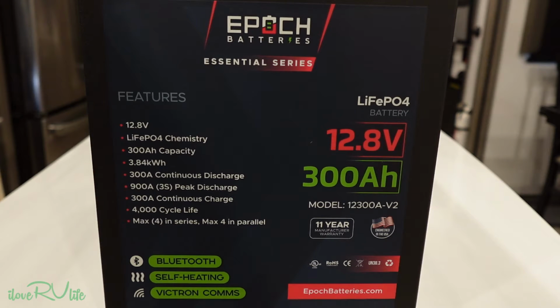As for electrical characteristics, it's a 300 amp hour battery with a maximum continuous discharge of 300 amps, a maximum charge current of 300 amps, and a maximum discharge peak current of 900 amps. It will support 4 batteries in parallel and 4 in series — think about that, 48 volts at 300 amps, or a massive 1,200 amp hours of capacity. The operating voltage ranges from 10 volts to 14.6.